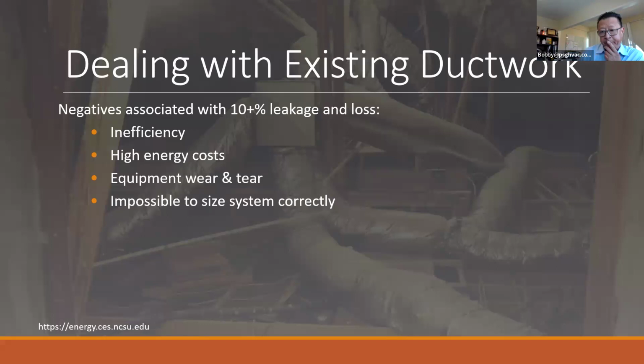The Energy Code has something to say on this too. They say that for altered duct systems, they need to be brought up to a maximum 10% leakage, and they're tested, right? Our HERS raters are out there day in and day out, putting these duct systems under pressure and measuring the leakage. So my rule of thumb is if you can achieve that 10%, then you're probably all right. If you can't achieve that 10%, then that's probably a sign to go replace that ductwork, and it's certainly a best practice to replace old ductwork.